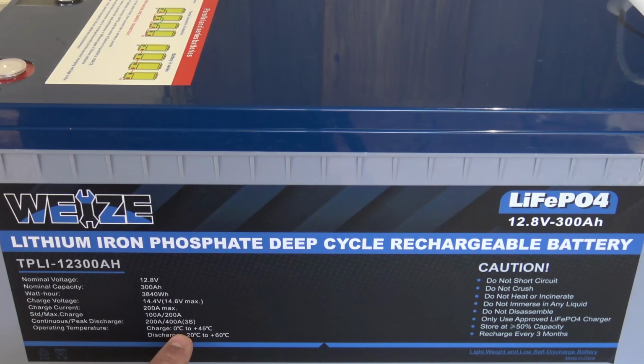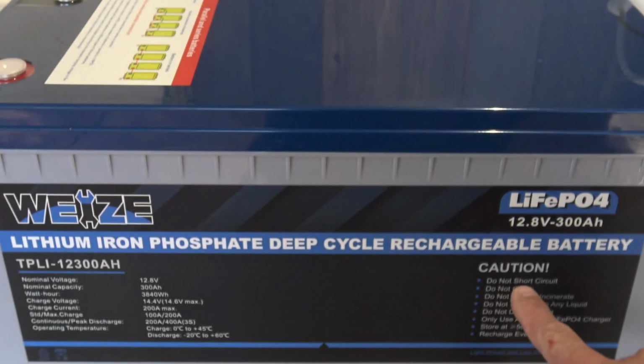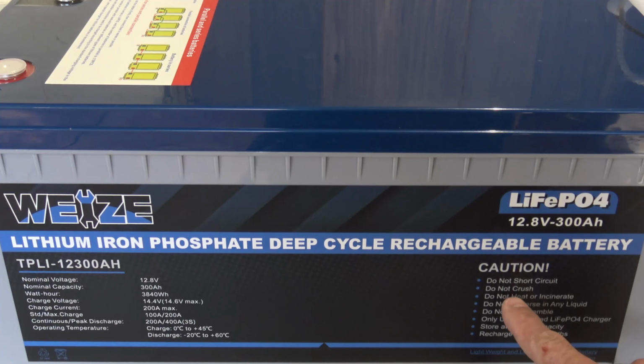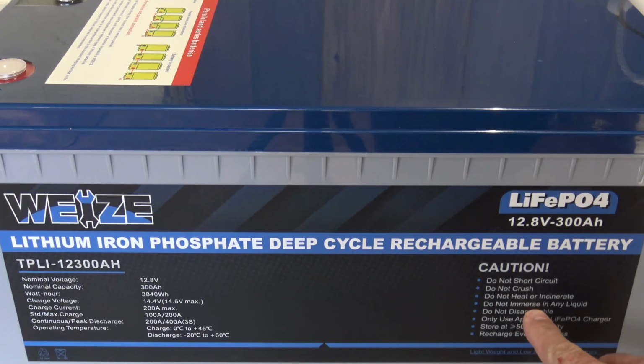The operating temperature is between 0 degrees centigrade up to 45 degrees centigrade. Discharge temperature is minus 20 centigrade up to 60 degrees centigrade. Over here it says: caution, do not short circuit this battery, do not crush it, do not put it in heat or incinerate it, do not immerse it in liquid, do not disassemble. Only use approved lithium iron phosphate chargers - that's a big one. Store at least 50% capacity and recharge this battery every 3 months. Lightweight and low self-discharge battery.